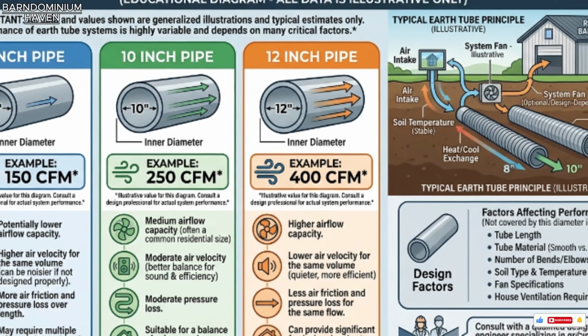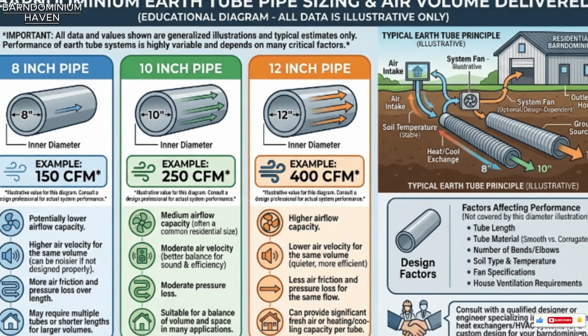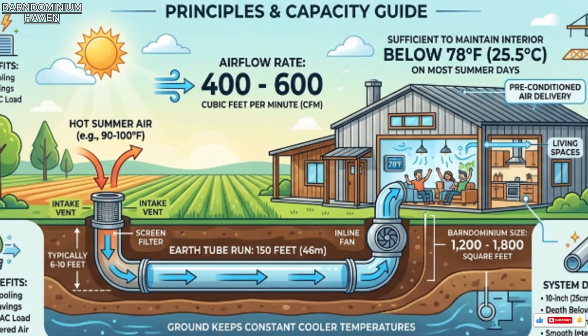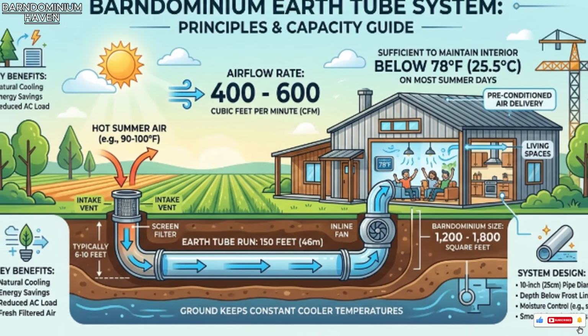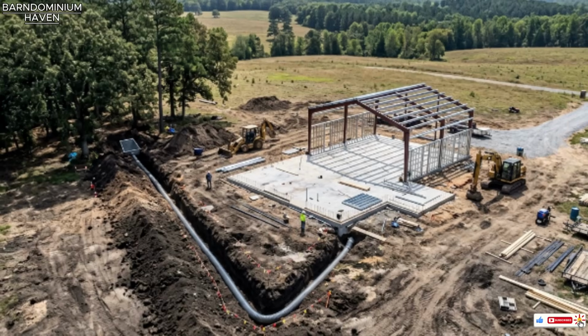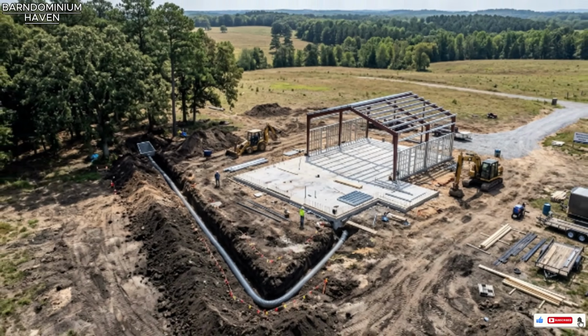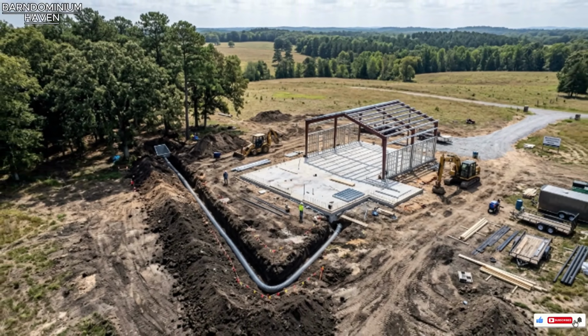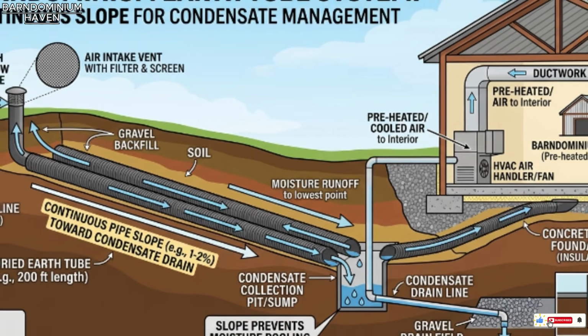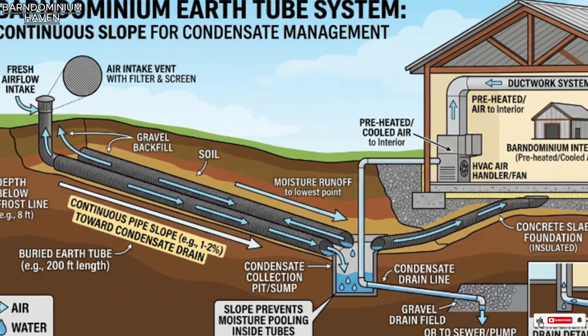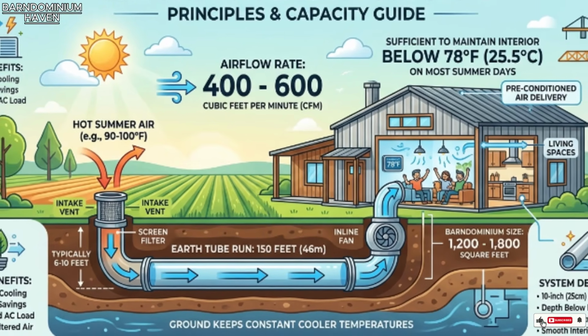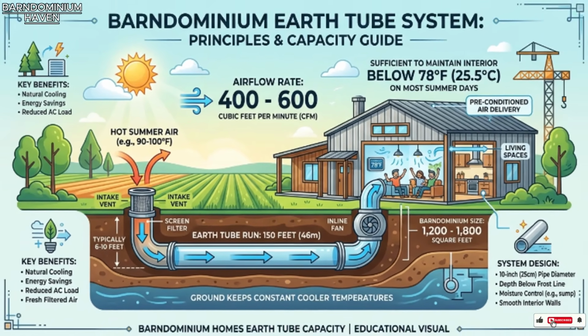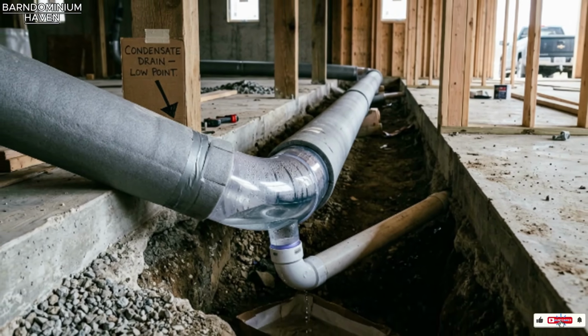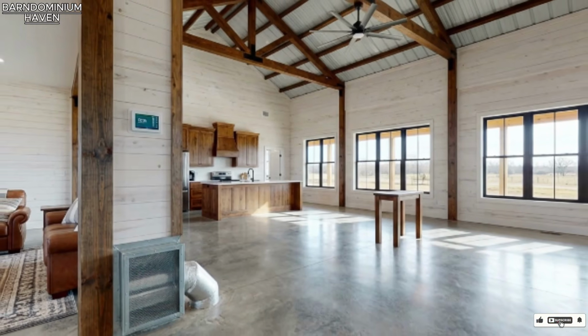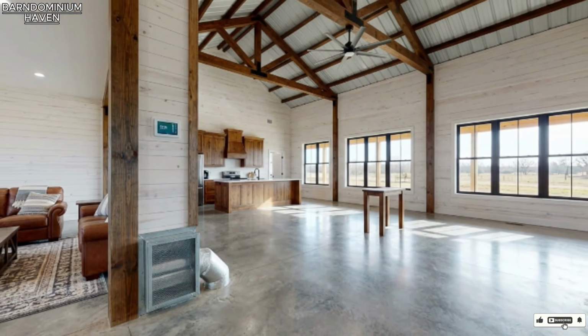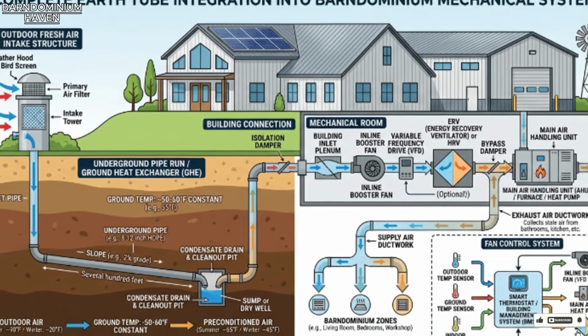The pipe diameter, typically 8 to 12 inches for a residential application, determines the volume of air the system can deliver. And that volume determines whether the earth tube functions as the primary cooling strategy or as a preconditioning system that reduces the load on a conventional HVAC system. For a 1,200 to 1,800 square foot barndominium, a single 10-inch earth tube run of 150 feet can deliver approximately 400 to 600 cubic feet per minute of preconditioned air, sufficient, in a well-insulated building, to maintain interior temperatures below 78 degrees Fahrenheit on all but the most extreme summer days, without any additional mechanical cooling input.